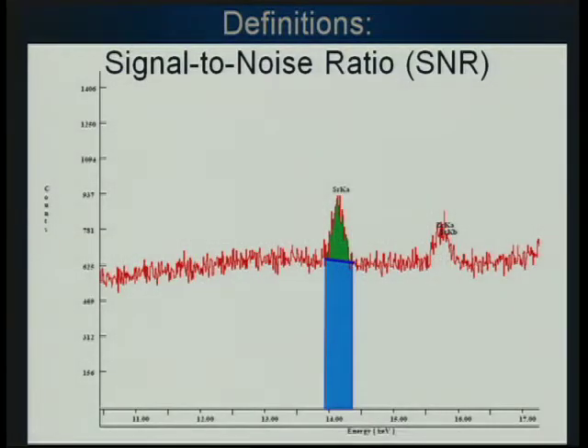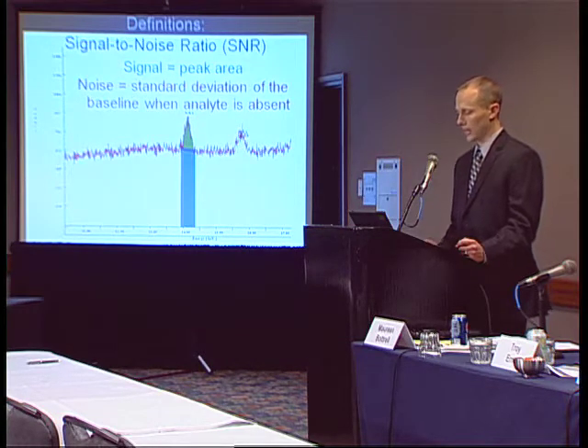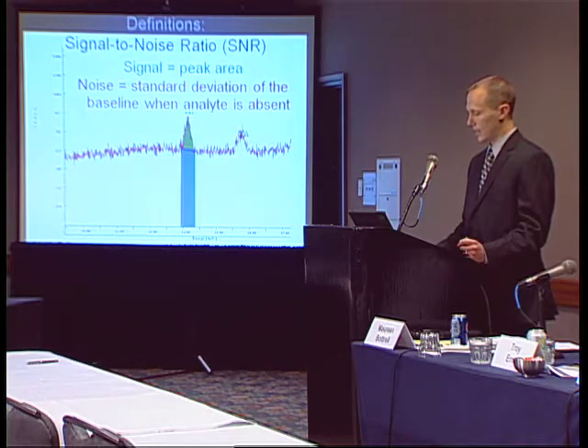Just a quick word of warning before we get going — statisticians, don't worry, you'll be fine here. The first term is signal-to-noise ratio. The signal is how much analyte is present; the noise is anything that interferes with that measurement — random fluctuations from the environment or from the instrument. Signal is often defined as the peak area; the noise in most typical applications is the standard deviation of the baseline when the analyte is absent. The signal-to-noise ratio is simply signal divided by noise.